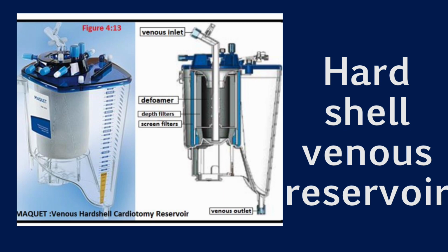Hard shell venous reservoir. A hard shell venous reservoir consists of a venous inlet and venous outlet, defoamer, depth filter, and screen filter.